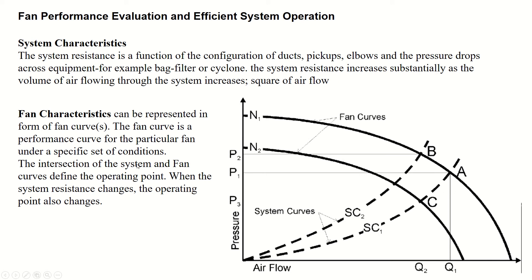The intersection of fan curves and system curves defines the operating point. When the system resistance changes, the operating point also changes. In this figure, the system curves are shown by dashed lines and the fan curves by solid lines. The intersection points of these curves are the operating points at which the fan will be operated.